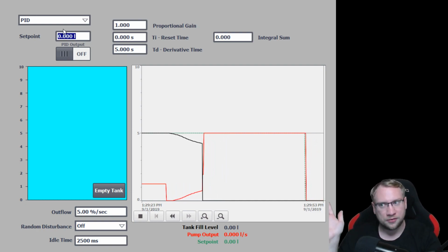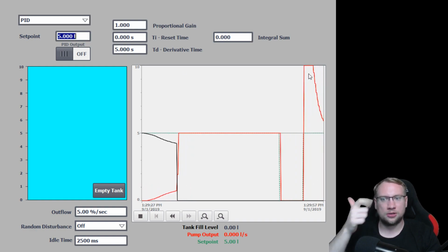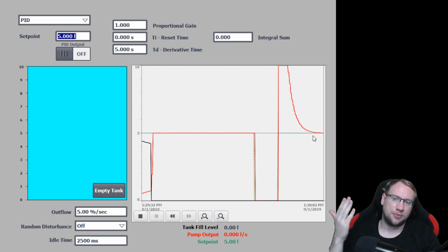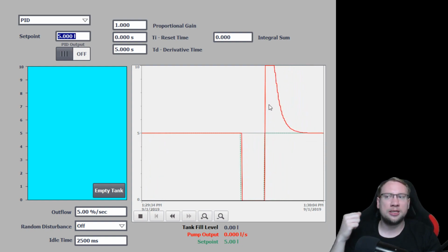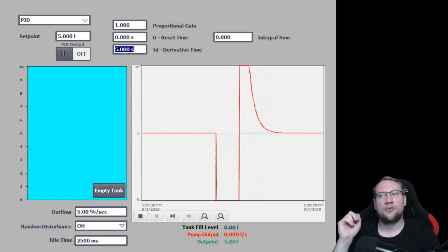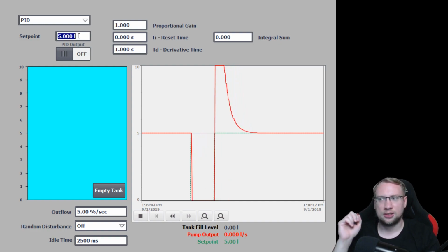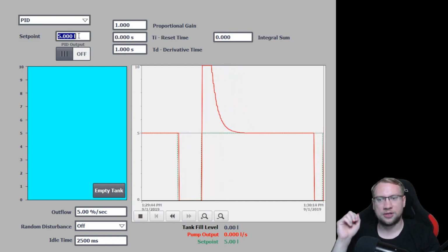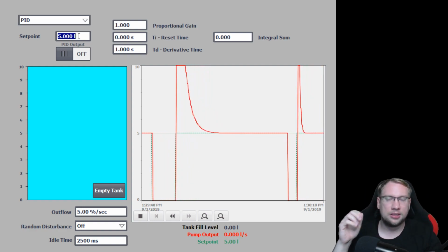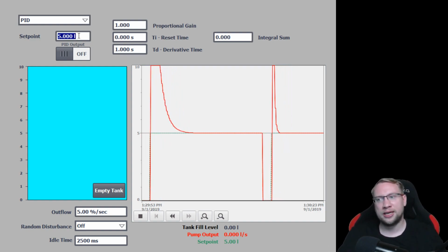But if I put it to 5 now, you will see, oh, my output is on for 1, 2, 3, 4, 5 seconds. Right? So my output will be increased on a change of an error. Right? And for as long as we set the time here, if I just set this for 1 second, and I go to 0 and I go to 5 again, 1 and we are directly there again, right? It adds on top of an error change.